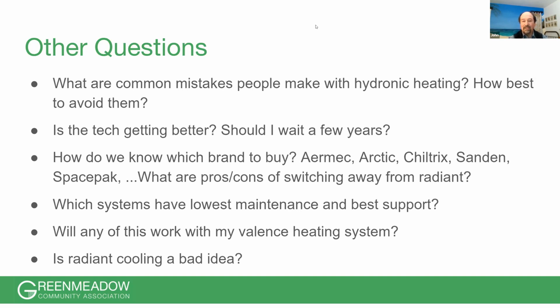So like when we do hydronic heating, you know, like a 20 or 30 degree delta, it'll short cycle a Sanden type unit, and it will try to kill itself, and then operate very inefficiently, less than 2. You know, a little bit more than 1 COP, but less than 2 when it has close returns.